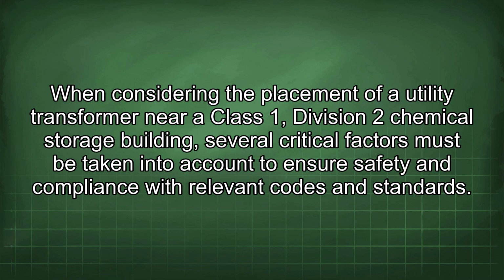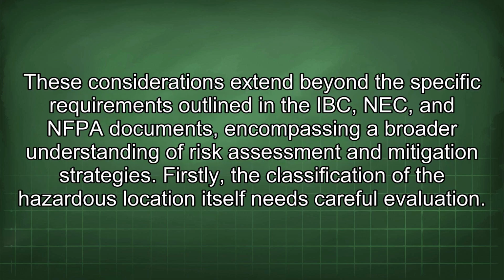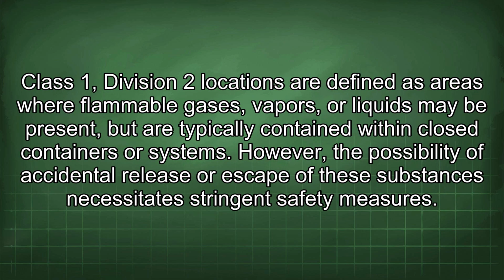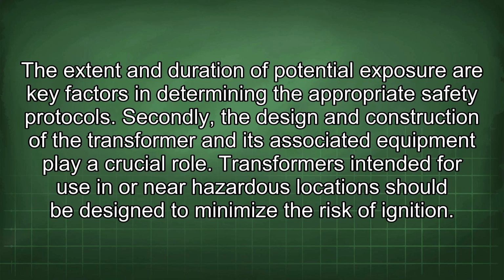When considering the placement of a utility transformer near a Class 1, Division 2 chemical storage building, several critical factors must be taken into account to ensure safety and compliance with relevant codes and standards. These considerations extend beyond the specific requirements outlined in the IBC, NEC, and NFPA documents, encompassing a broader understanding of risk assessment and mitigation strategies. Firstly, the classification of the hazardous location itself needs careful evaluation. Class 1, Division 2 locations are defined as areas where flammable gases, vapors, or liquids may be present but are typically contained within closed containers or systems. However, the possibility of accidental release or escape of these substances necessitates stringent safety measures. The extent and duration of potential exposure are key factors in determining the appropriate safety protocols.